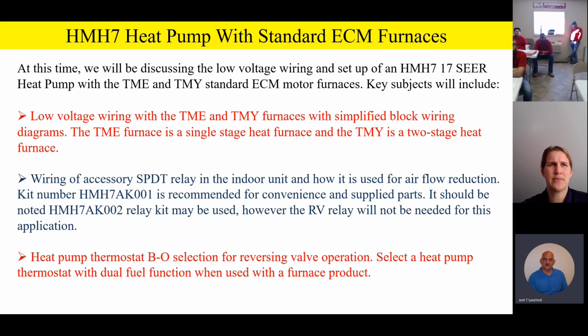All right, so that kind of rolls us into just using regular furnaces. Now, if you guys don't do a lot of furnace product, we'll kind of breeze through this a little bit. But basically, if you're going to put these on a dual fuel application with the furnace, remember, you're still going to use the relay kit. And the TME and the TMY furnaces: the TMY is a 2-stage heat, and the TME is a single-stage heat furnace. You're still going to use the relay.